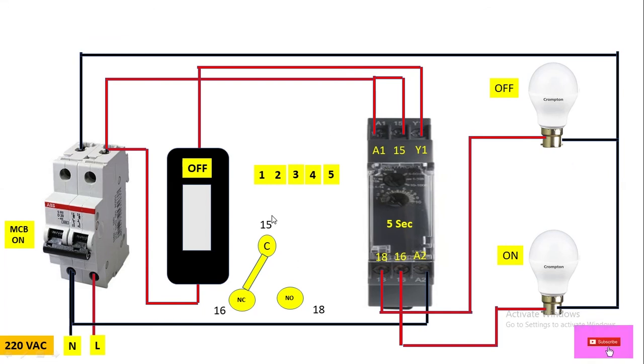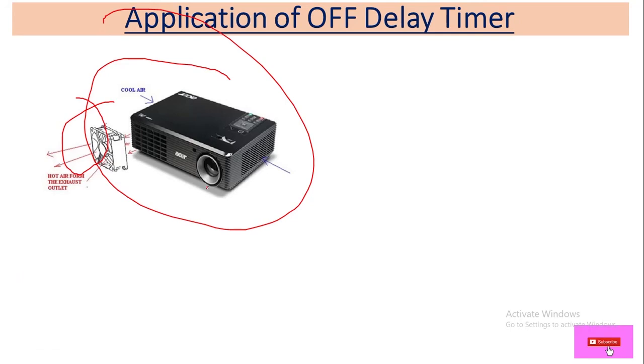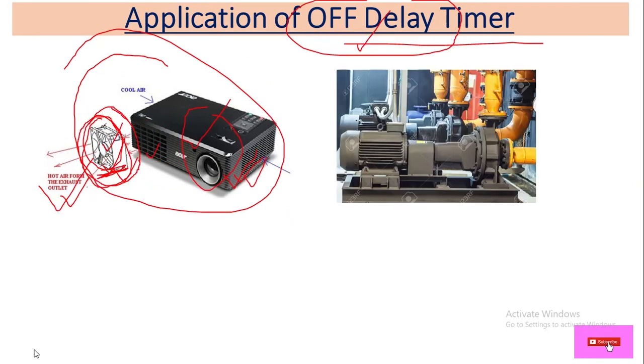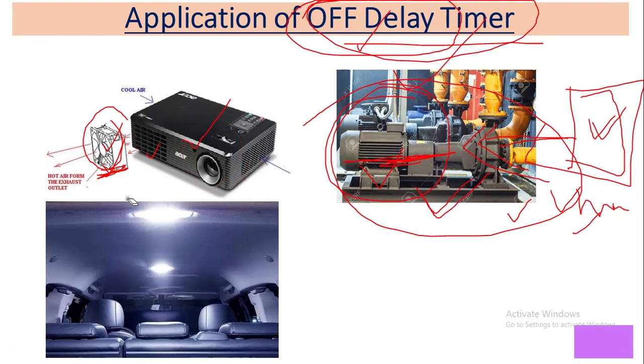So that is how the off-delay timer works: after you switch off, the contacts maintain their state for the set delay period — here five seconds — then revert to normal. A practical application is a projector cooling fan: when you switch off the projector, after a few seconds only then will the cooling fan turn off. Another application is a chiller plant condenser pump, which stays running for some time after the chiller is switched off.